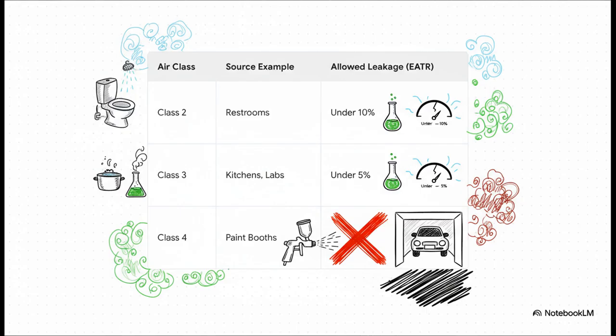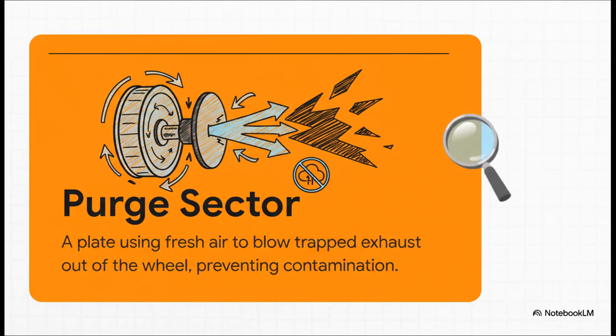So less than 10% of the bad air can mix with the good. For more contaminated Class 3 air, from kitchens or labs, it has to be under 5%. And for the really hazardous Class 4 air, nope. Zero leakage allowed. You can't even use a wheel, period. So how do engineers meet those super strict leakage standards?